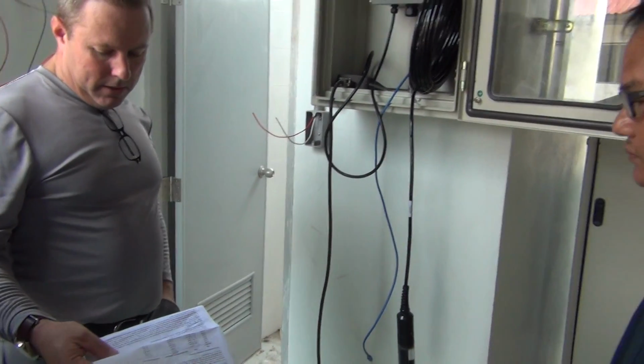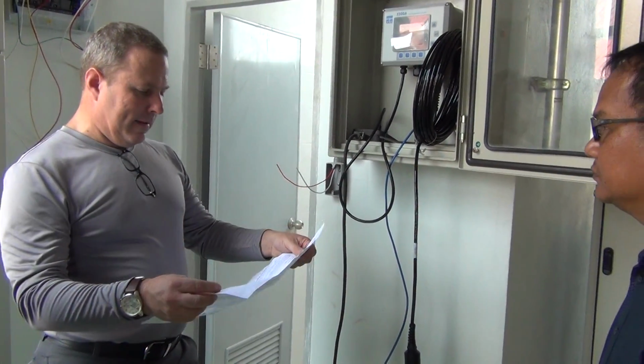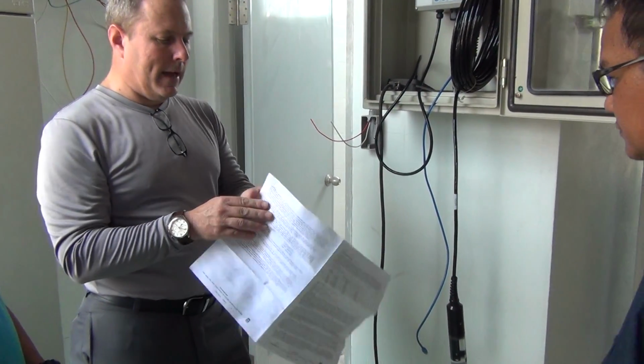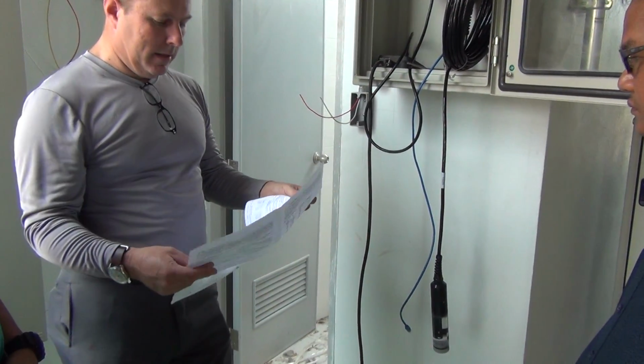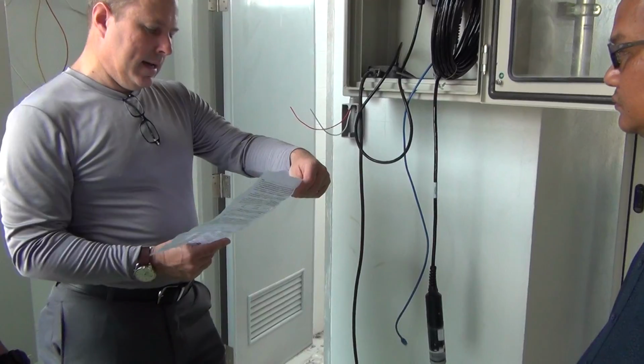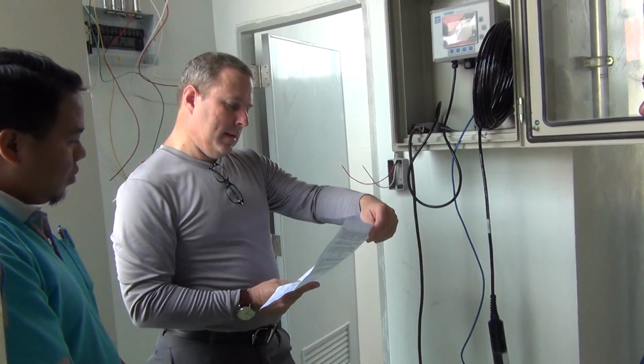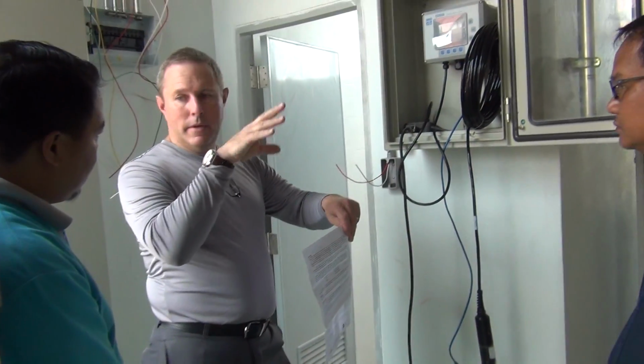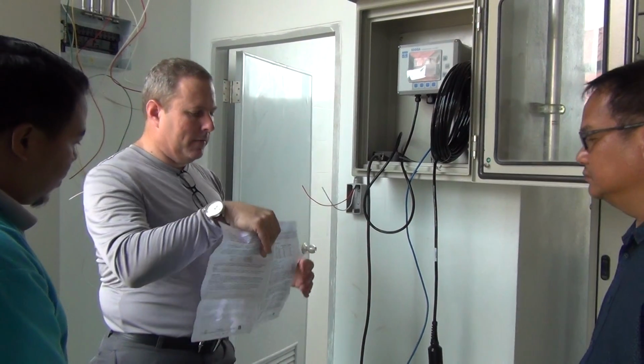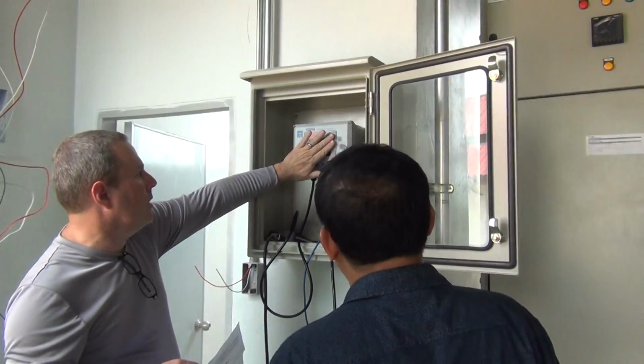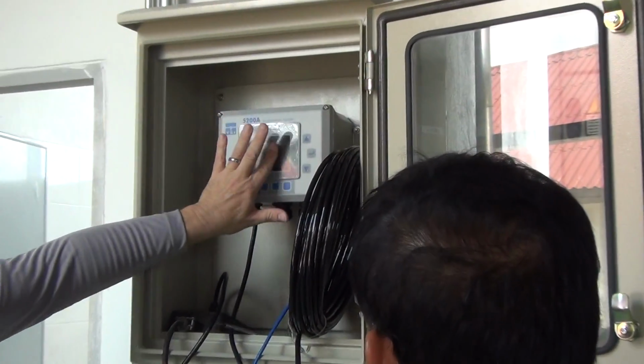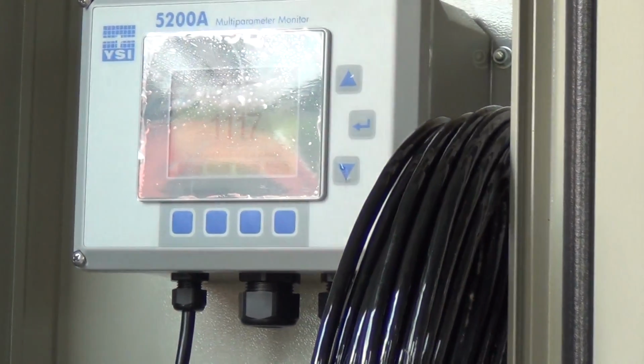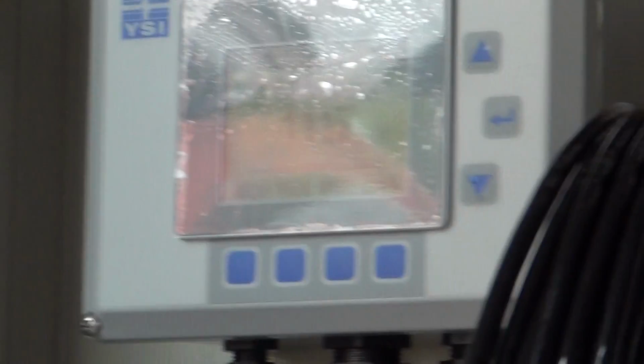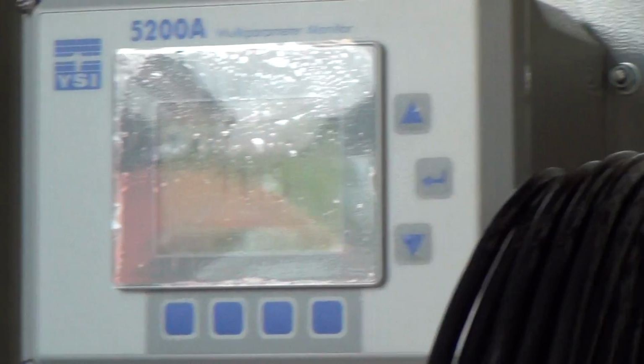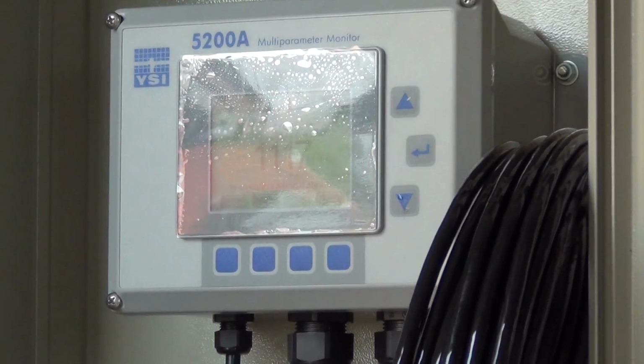So let's do a quick calculation and determine. I used to have a pre-printed sheet that had the temperature and the value, but I don't see that on this one, so I'm going to have to calculate. I will send you a simple chart that you can use that has the temperature, and you just cross-reference and it will give you the value. Because when we actually calibrate it, this is just a protective plastic that we can leave until they're ready to take it off. You'll put that value in because we have to temperature compensate. Actually, it's saying on the 5200A, we don't have to temperature compensate. The unit does it for us.